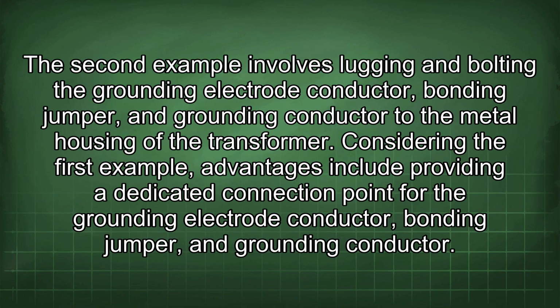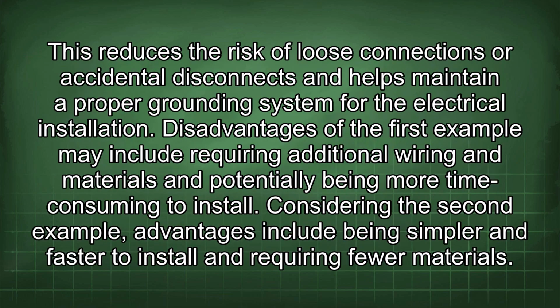The second example involves lugging and bolting the grounding electrode conductor, bonding jumper, and grounding conductor to the metal housing of the transformer. Considering the first example, advantages include providing a dedicated connection point for the grounding electrode conductor, bonding jumper, and grounding conductor. This reduces the risk of loose connections or accidental disconnects and helps maintain a proper grounding system for the electrical installation.